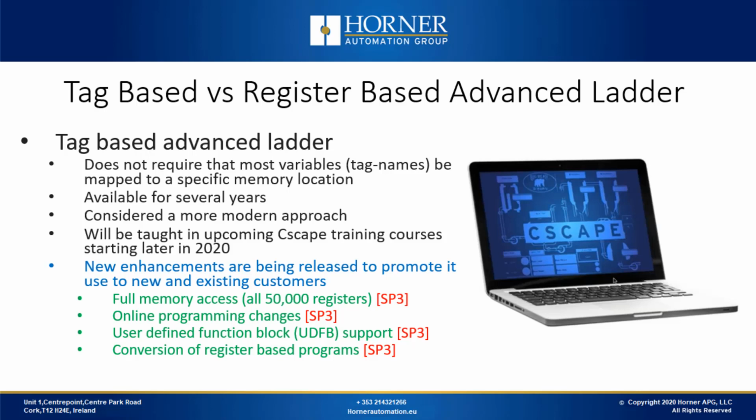The tag-based approach is certainly considered the more modern approach. There are also several new enhancements being released that should promote the use of tag-based logic. First of all, we're eliminating the restriction on the number of registers. As with register-based logic, you're capped at 10,000 registers, but with tag-based, you can now use up to 50,000. So with the introduction of Service Pack 3, you'll have full memory access.